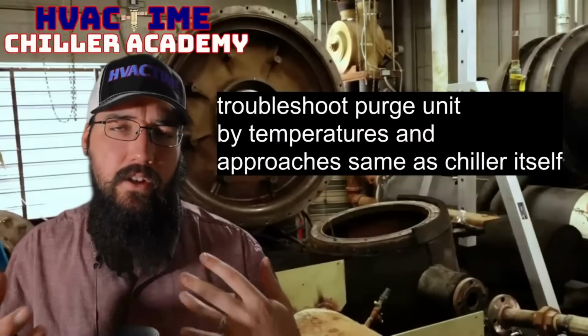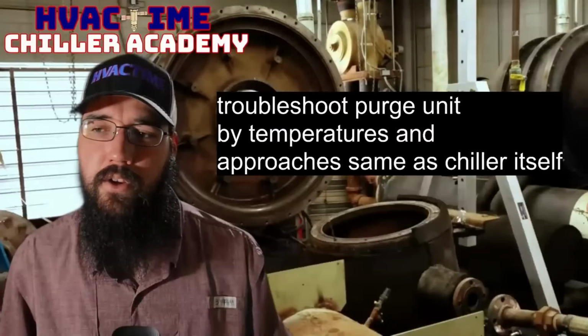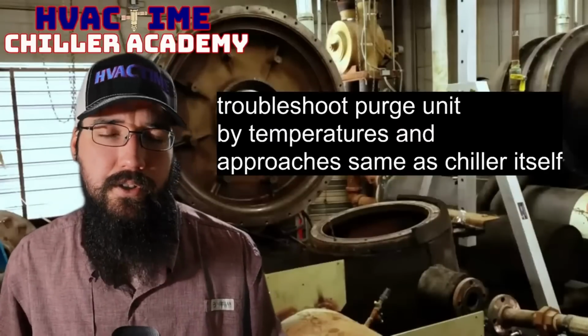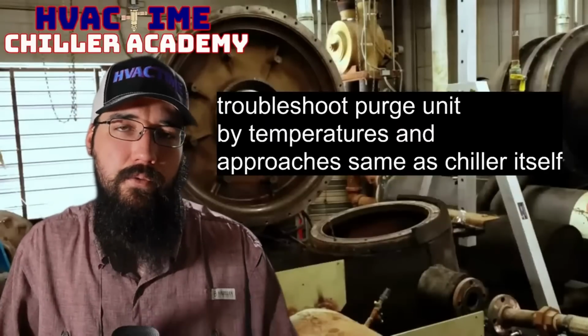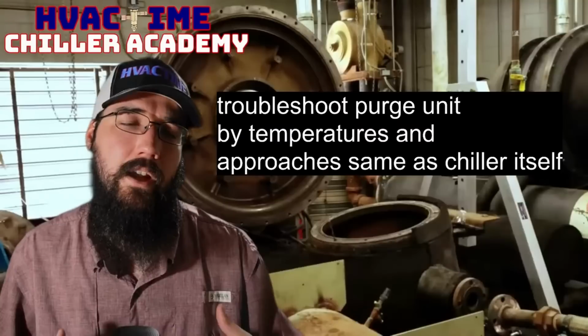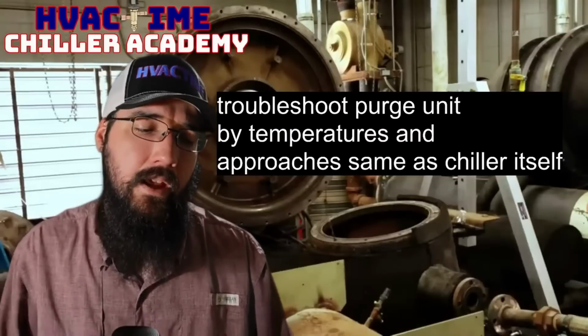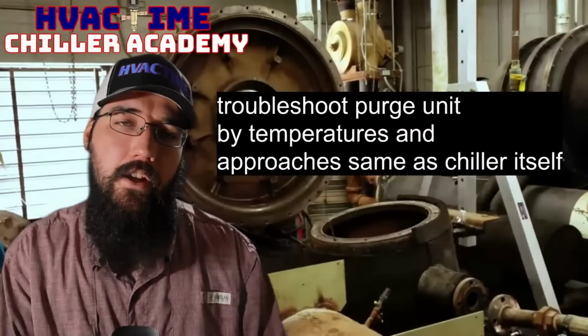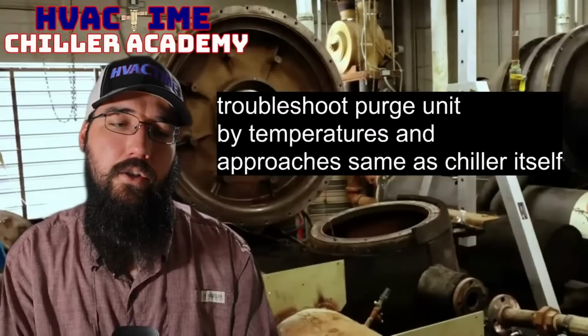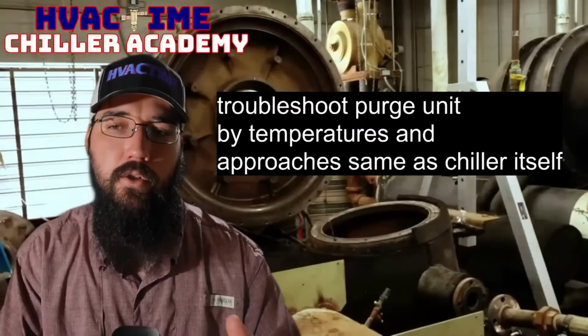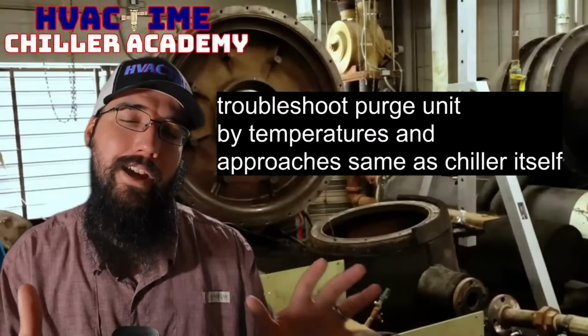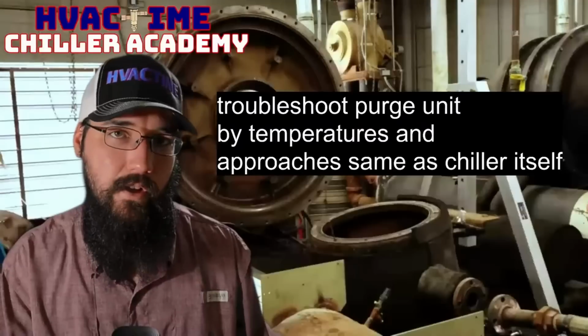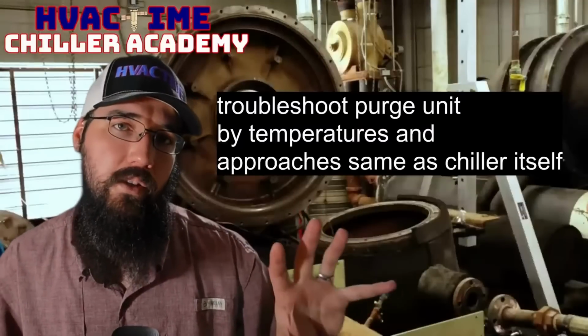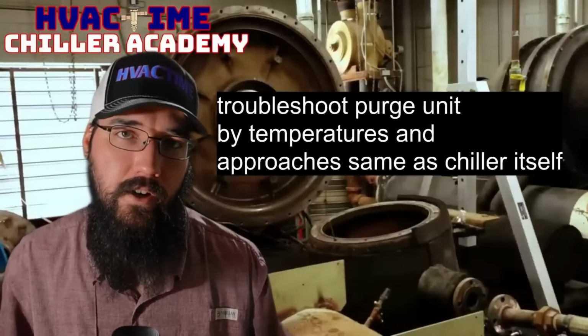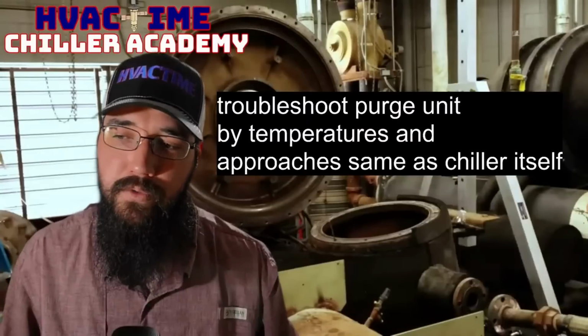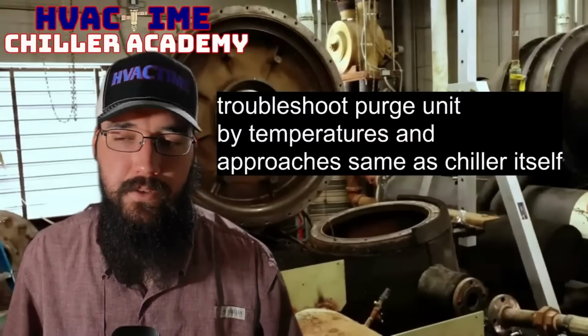In my opinion, you don't troubleshoot those the same way you would a regular little refrigeration unit or system. Granted, if you're used to working with small appliances, like I did at one point early on, you didn't hook up to those either. You took your temperatures, you looked at a lot of different variables without actually tampering with the refrigerant circuit itself. And that was always the worst case, last thing you did scenario. But the approach values and such just don't quite line up the same for those.